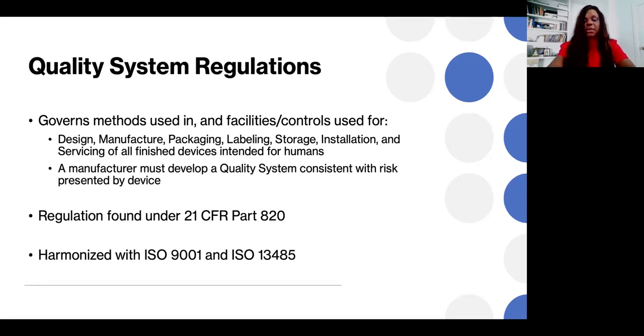We want to just talk briefly about the quality system regulations. And it tends to be a little confusing because a lot of individuals may believe that the QSR does not apply if they have an exempt product. This is not true, because if you are making and selling a medical device in the US, the QSR actually governs the methods and the facilities and the controls that are used for your design, manufacture, packaging, labeling, storage, installation, and servicing. And it's for all finished devices that are intended for humans. So it's very important that you understand how the QSR applies to your device.